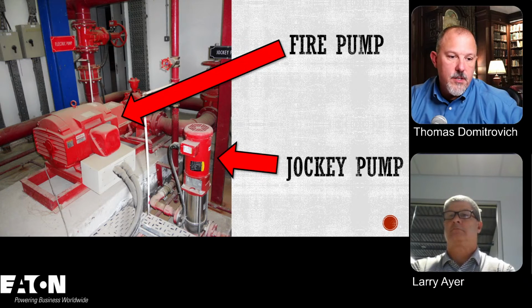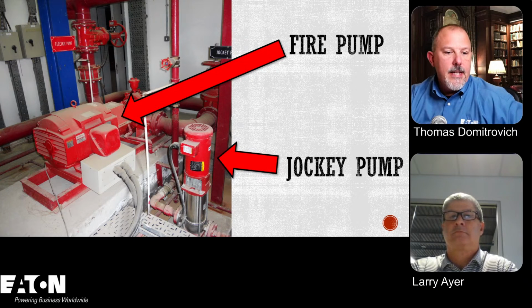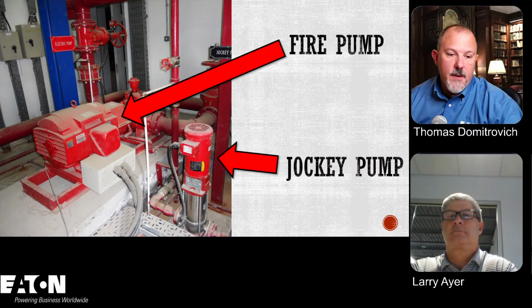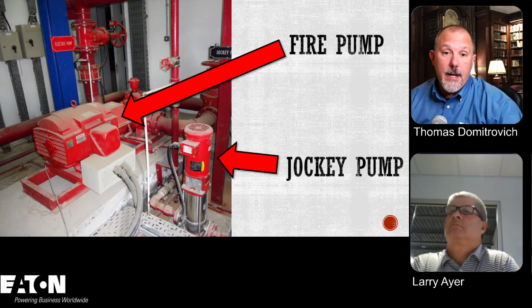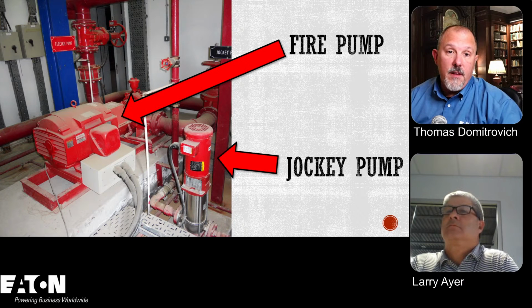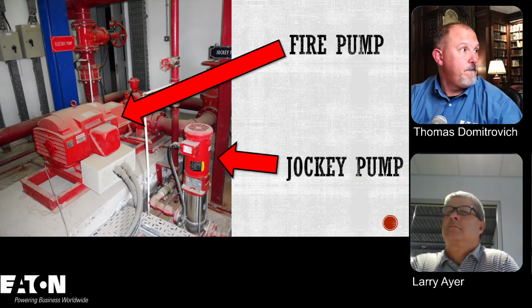Good question. Don Ganir says he's done a couple with both electric and diesel fire pumps in the same pump house building. Can't really put one outside up here where it gets cold. So I guess that's the other condition Don pointed out: the environmental conditions that you're putting this motor into probably make a difference as well. If it's going to get cold, if it's going to freeze, and you've got water and all that other good stuff that you're worried about, there are all those environmental conditions you have to think about.